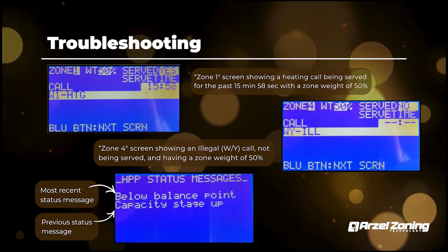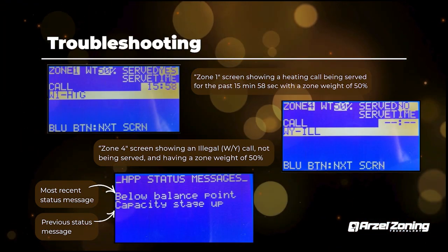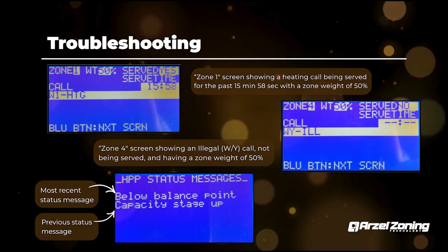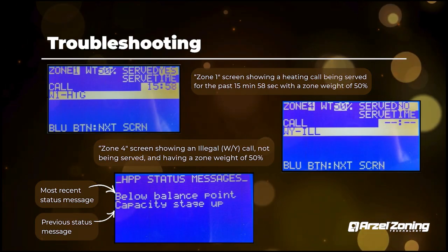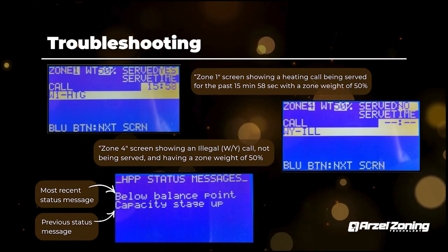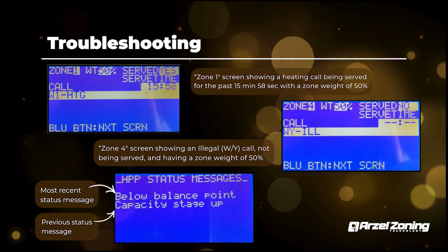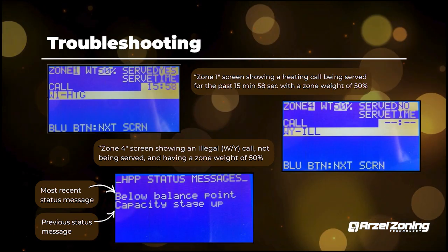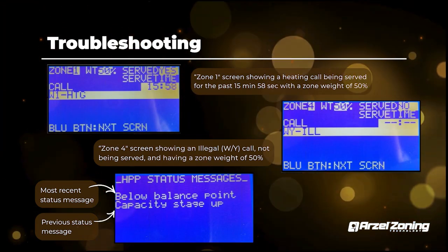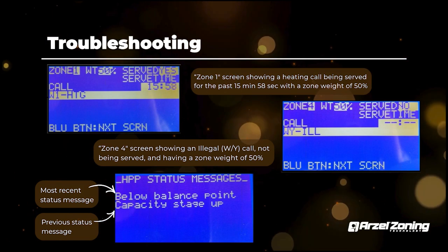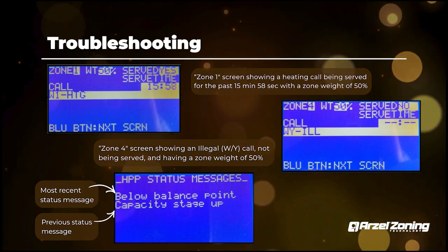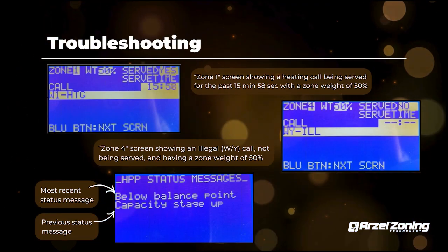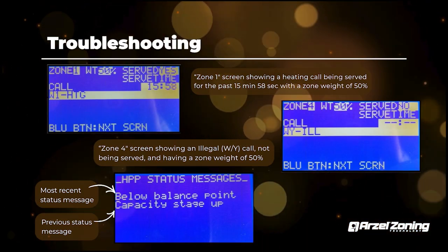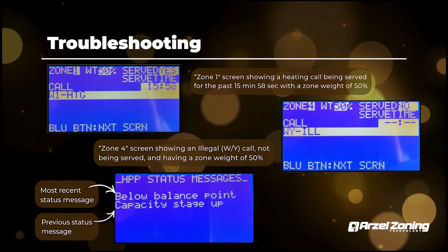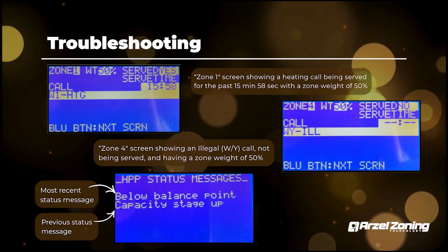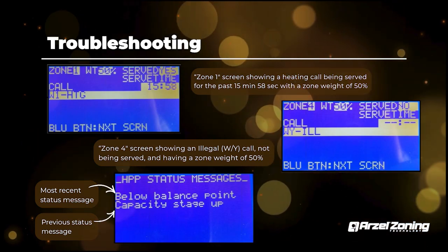So in this case, they either have a short in their thermostat wire between W and Y, or they have it set up to energize as a heat pump for that call. And you can't do that with the HeatPumPro. It has to be heat only, heat cool calls. So anytime you see ILL, for whatever matter, that's what that means. If you ever see a Y-ILL, it's because you're not energizing your fan with a cooling call. All cooling calls, you have to energize Y and G from your thermostat. So if you ever see that, that's why. It's either a bad thermostat relay or that particular thermostat doesn't have that function, which is really uncommon, but every once in a while, some of the real cheap thermostats won't output Y and G together. So just keep that in mind as well. That's what that would be.